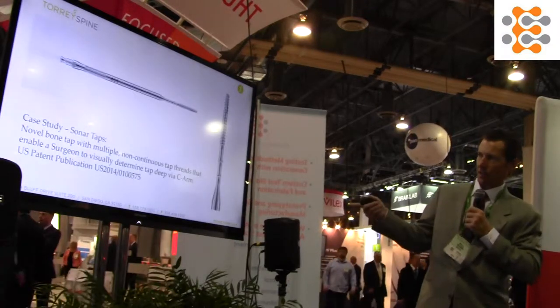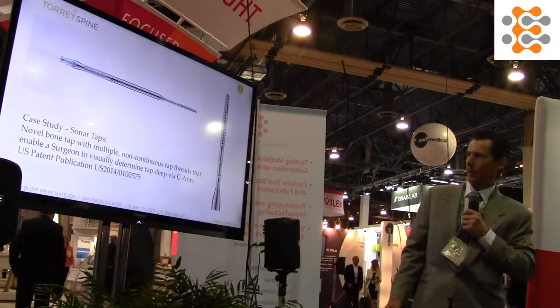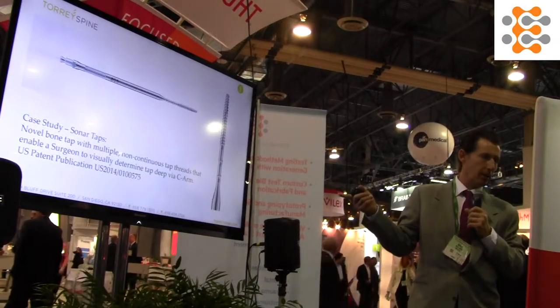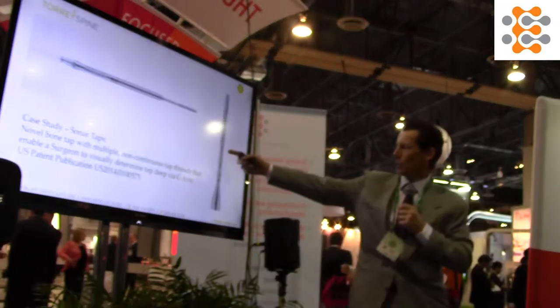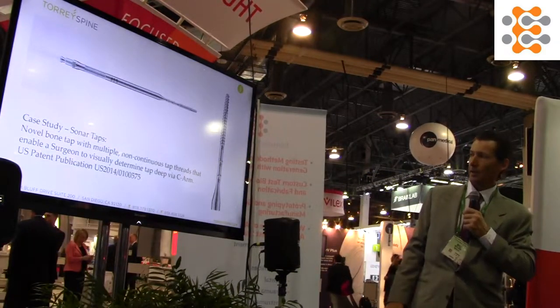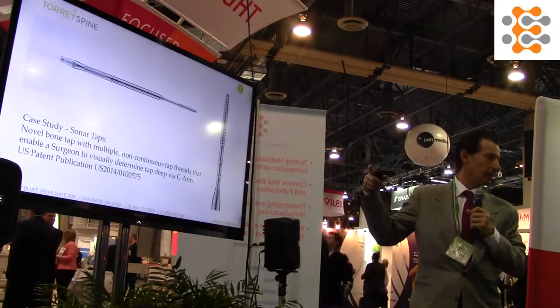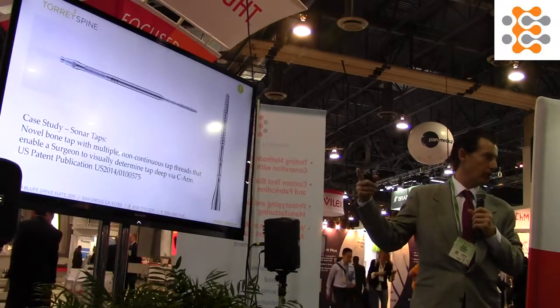This is a case study — something we developed at TorreySpine, one of the companies I'm working with. They developed a tap for putting in a pedicle screw for either MIS or open surgery. This tap has a segment where there are gaps — we purposely have gaps at 35, 45, and 55 millimeters. So as you advance this tap, by taking fluoroscopy, you can see the depth of the tap and then determine the screw you might want to use to implant in the pedicle.